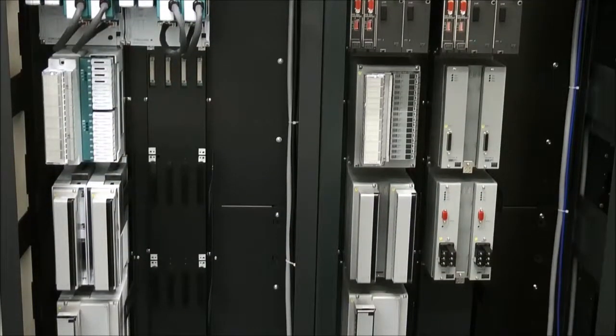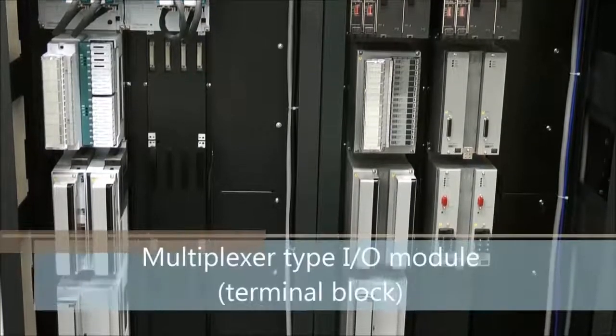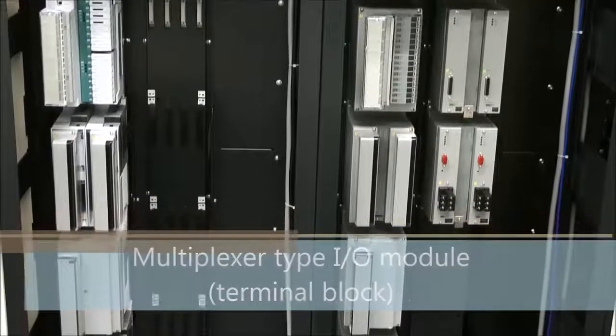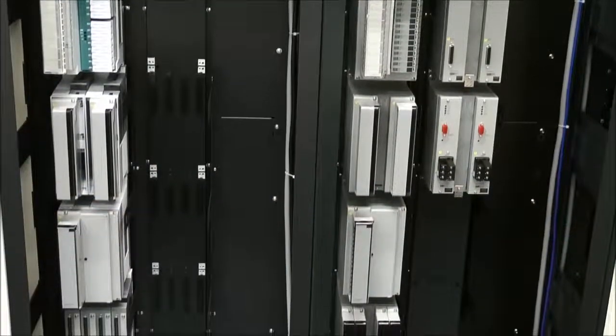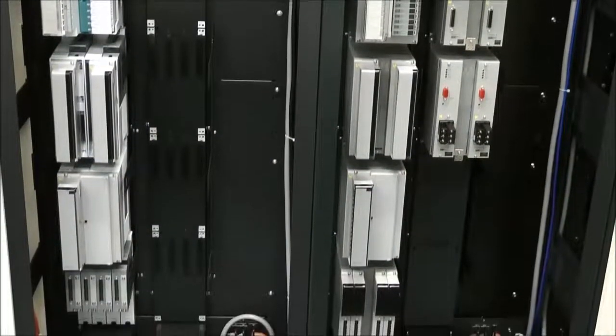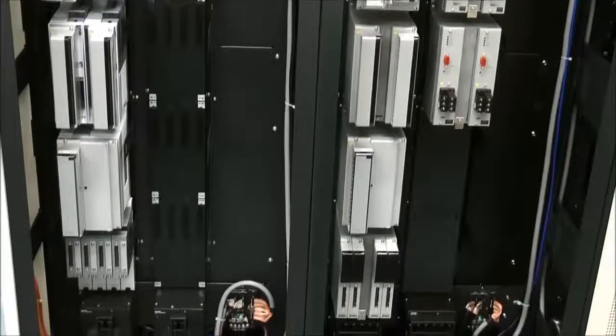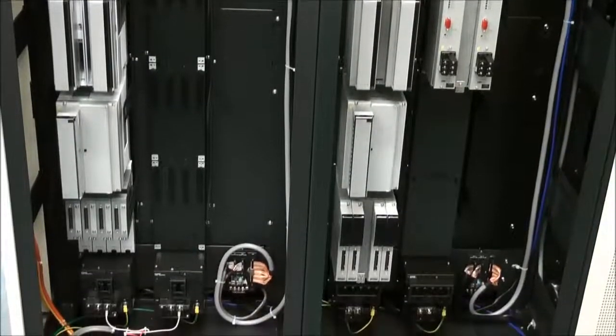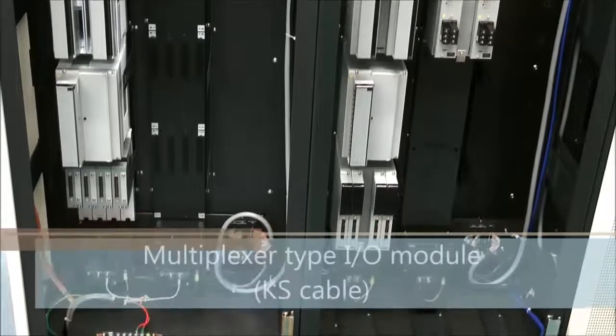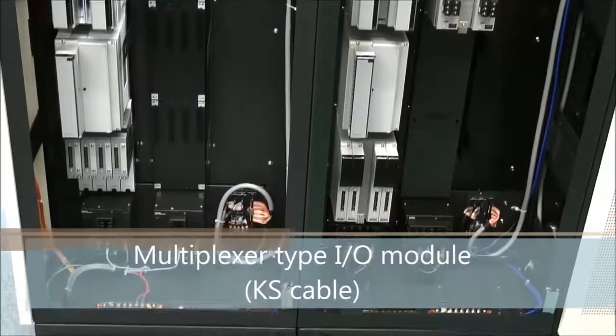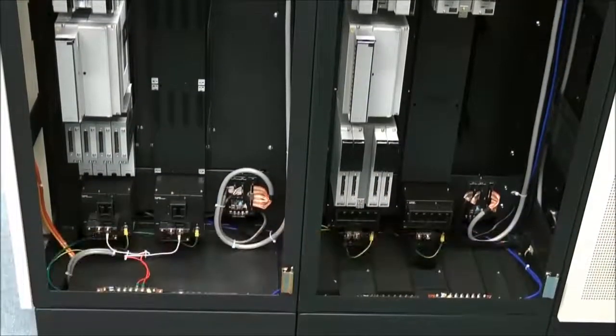A single unit supports 16 points. Each multiplexer module consisting of multiple points will be replaced with a new module that supports the same signal types and the same number of points. The terminal block connected with field cables will still be used after upgrade. Some multiplexer modules are connected with cables, and they again will be replaced with modules supporting the same signal types and the same number of points.